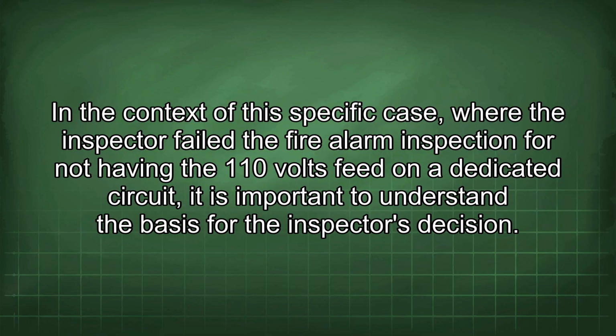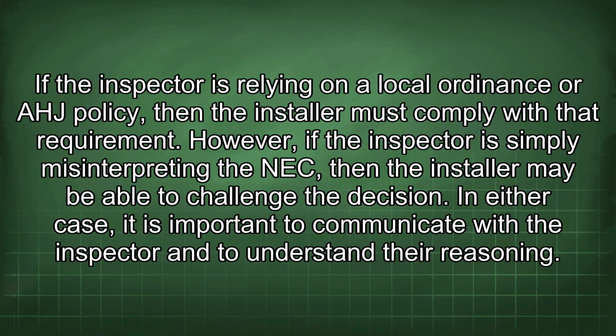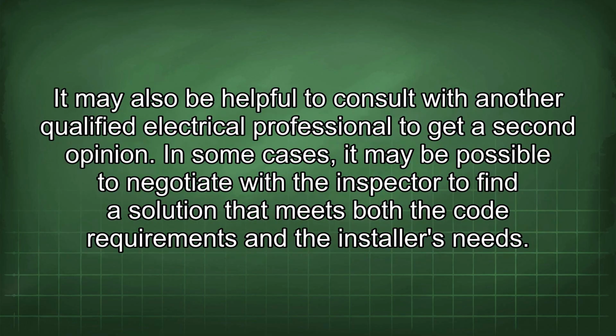In the context of this specific case, where the inspector failed the fire alarm inspection for not having the 110 volts feed on a dedicated circuit, it is important to understand the basis for the inspector's decision. If the inspector is relying on a local ordinance or AHJ policy, then the installer must comply with that requirement. However, if the inspector is simply misinterpreting the NEC, then the installer may be able to challenge the decision. In either case, it is important to communicate with the inspector and to understand their reasoning. It may also be helpful to consult with another qualified electrical professional to get a second opinion.